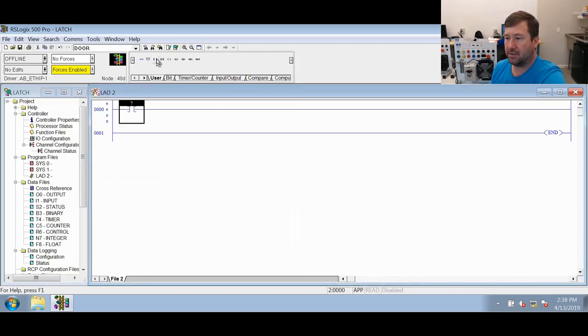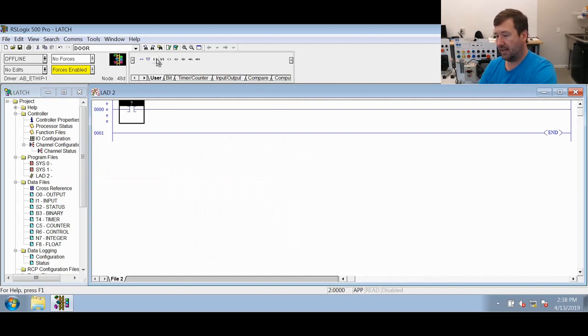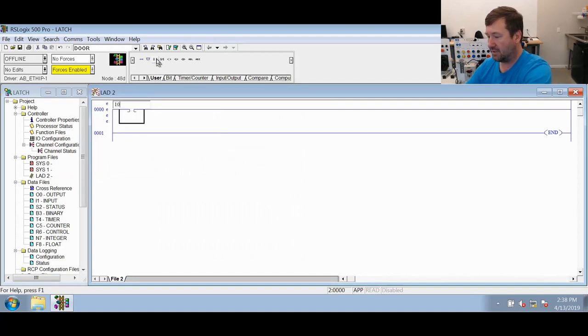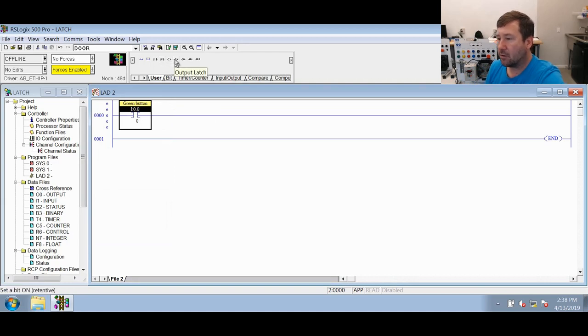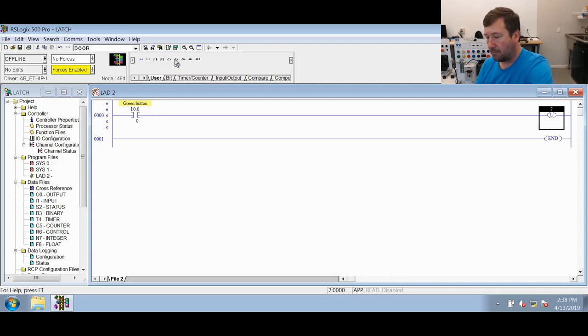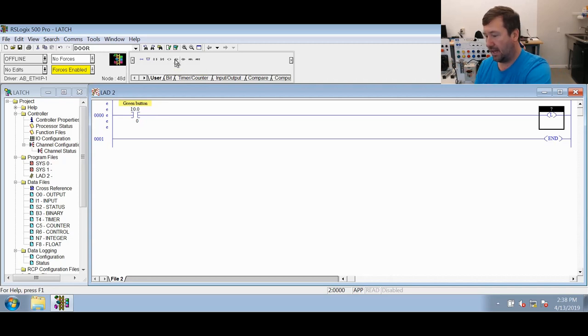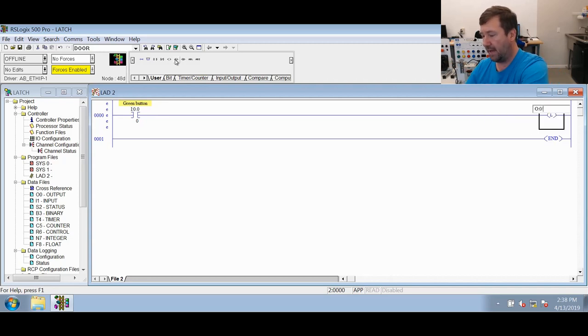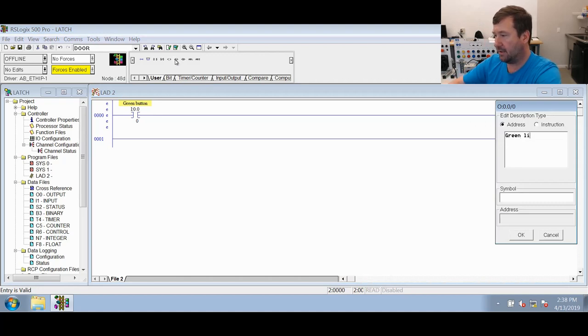Now we're going to insert an XIC instruction. We're going to look at this green button here, and that is connected to I:0/0. Let's call it the green button. We are going to use an OTL output latch instruction, and we're going to latch our green light, which is O:0/0. We'll call that the green light.